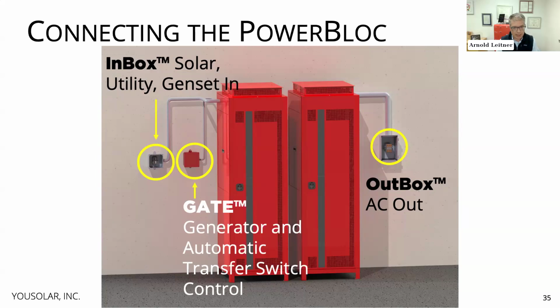The gate has cards inside that are unique to different generators and different transfer switches. Once we know what transfer switch and generator you use, we insert the right card that communicates with that particular device. If in the future that generator or transfer switch changes, you just order a new card, we ship it, you swap it out, click it in, and now you can control that different type of generator or automatic transfer switch.